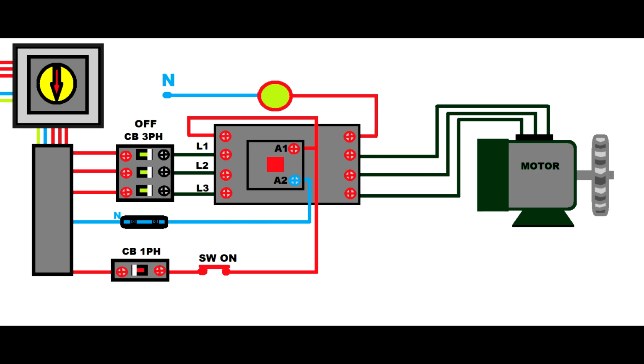This system allows the control circuit to remain active if the power circuit fails. Now let's look at another type of system in which the control circuit loses power if the power circuit breaker trips.